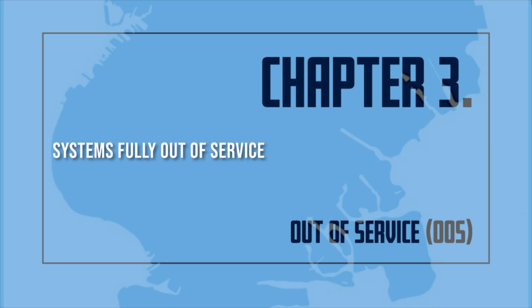Systems fully out of service. The impairment coordinator/building owner shall ensure that the local administrative fire company, a master fire suppression contractor, Class A or B, or a master licensed plumber, as restricted, has placed one white disc 8 to 9 inches in diameter on all affected fire department connections. A red tag shall be placed at the main control valve indicating the sprinkler company name, date of removal from service, and anticipated return to service date.